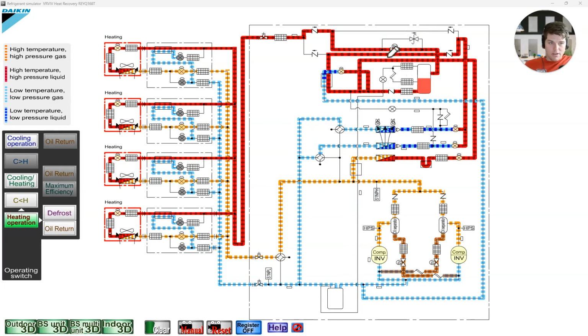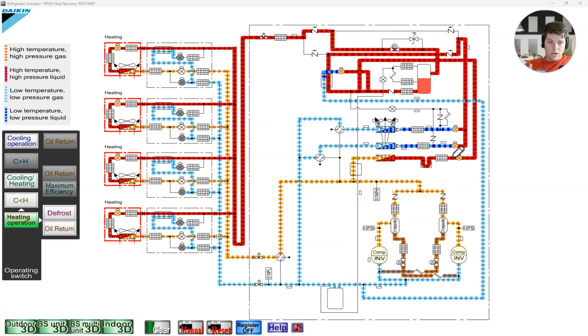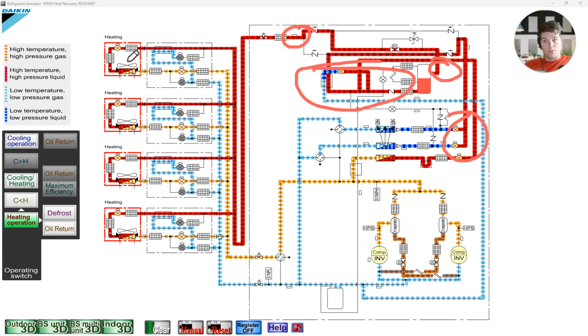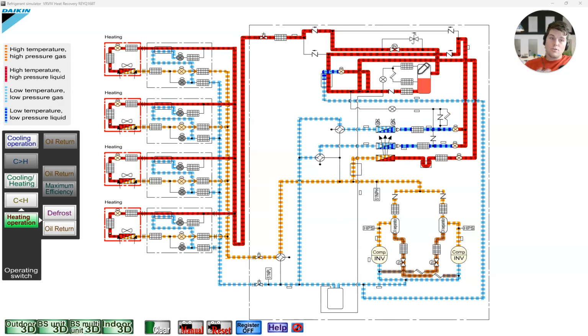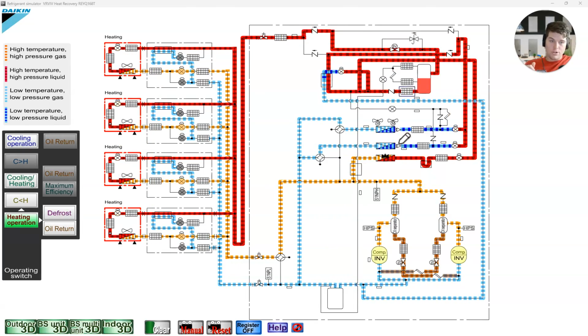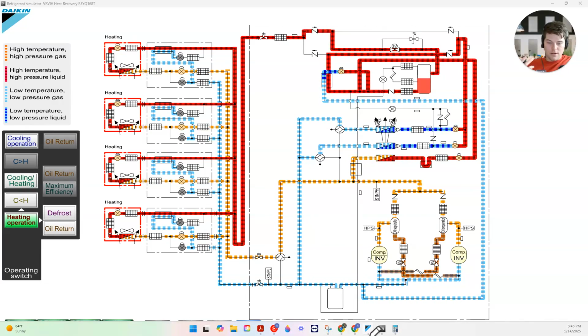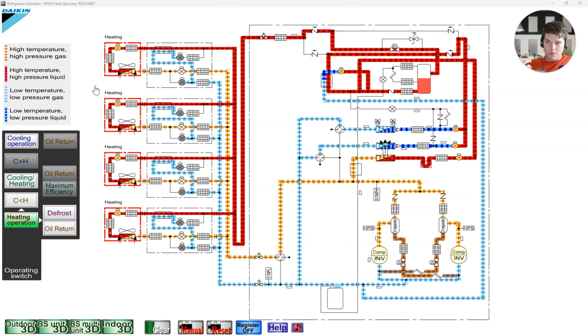Well, if you watched any of my other videos or have a basic concept of refrigeration, we should not be checking liquid coming right before my expansion valve. Nope. We shouldn't check it after my subcooling circuit. No. We should either check it entering my liquid receiver, entering my module, or leaving my heat exchanger. Now, leaving your heat exchanger is one of my favorite things to do because you can do an average between all the coils connected, which is a little bit of a pain in the butt, but worth it. But again, you can also check the quality of liquid coming back to the outdoor unit, which is what we're going to do.